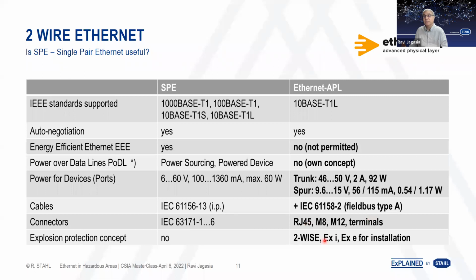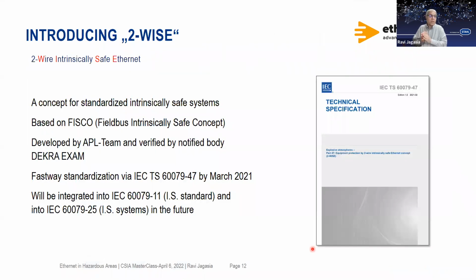Some of the standard connectors used, and the new standard of 2-WISE. Why did we do that? We'll come to that later. So the introduction of 2-WISE: why did we do two wires? This was a standard developed so that you could run two-wire twisted pair cables to your field devices, which run the Ethernet protocol, and it is intrinsically safe. It was based on the FISCO Fieldbus standard. It was tested by DEKRA, one of the notified bodies under IECEx, ATEX, and even for the American markets. It was very quickly adopted by March 21 by the IEC as a de facto standard, Part 47, which will later be integrated into the -11 and the -25 systems.